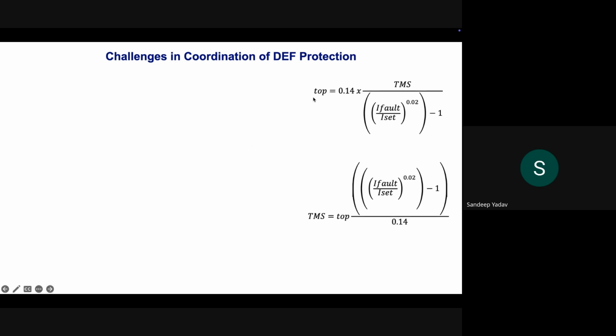This is the penultimate slide. So, directional earth fault protection. It is an IDMT based curve, so we have to set the plug setting multiplier and time setting multiplier. When we try to calculate the operating time, for the standard inverse curve the formula is 0.14 times time multiplier setting divided by (I fault, which is the fault current, upon I set, which is the pickup current of the relay) to the power 0.02 minus 1.